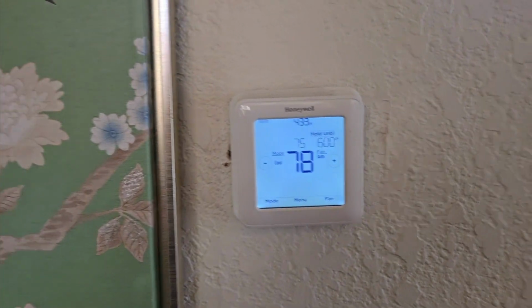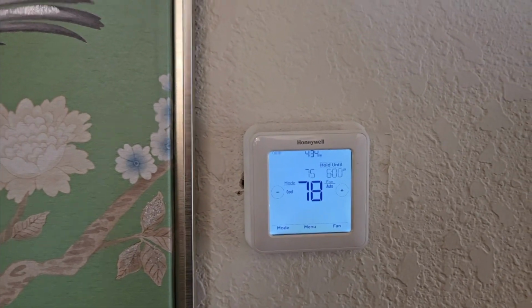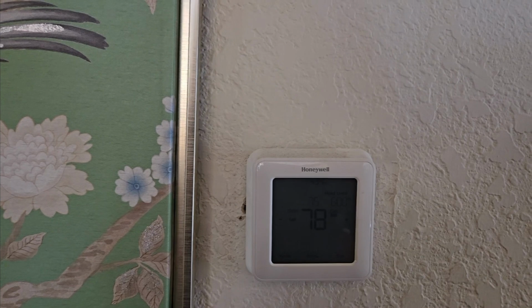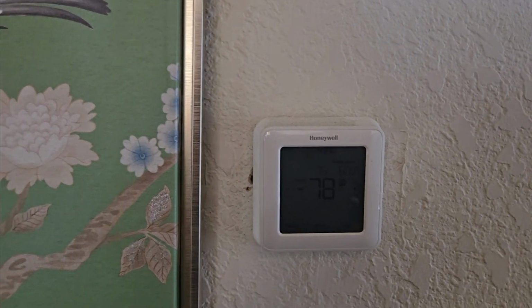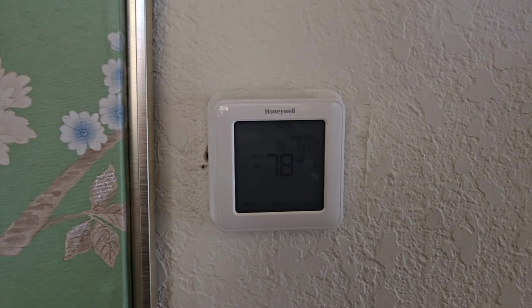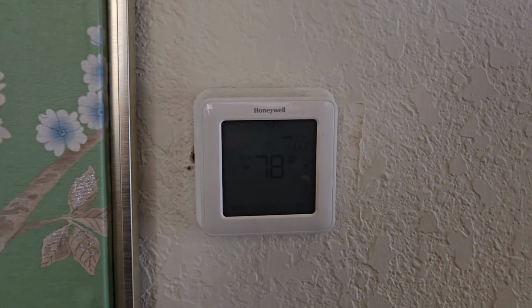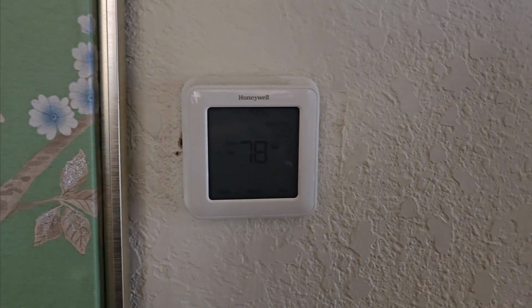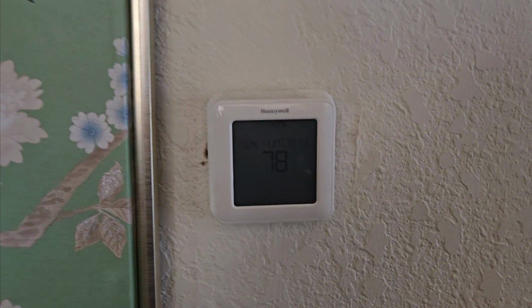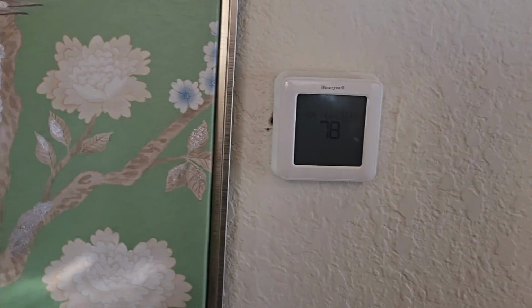Okay? So that means when you come over here to this little thermostat, and I set this for 75 degrees, and it's at 78 right now, that sends a signal not only to the fan up in the attic, but over to the fan on the compressor outside. It tells the compressor to kick on first and then the fan to kick on. There's no sense in the fan turning on if the compressor is not running, if that makes any sense. Because if you'll notice, one that's running properly and has the right amount of refrigerant, the fan on the compressor does not immediately come on when the compressor kicks on. It's usually a few seconds afterwards. First compressor, then fan. Then the fan in the attic will already be running, and bada bing, bada boom, you have cool air. So, in the next video, I'm going to take you up into the attic.